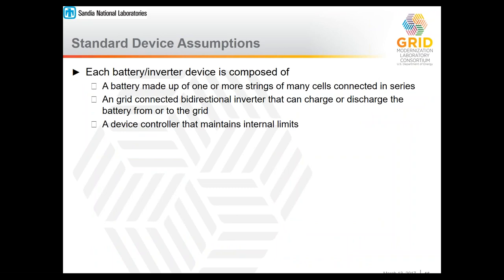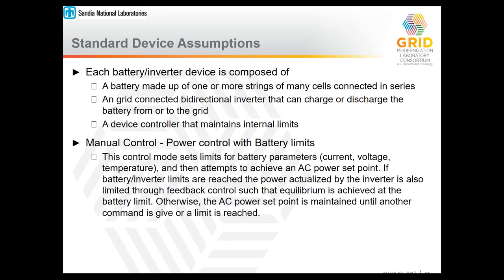So some standard device assumptions here. Just to further clarify what we're referring to, each battery and inverter device is composed of the battery itself, a bidirectional inverter that can both charge and discharge from the grid, and a device controller that maintains internal limits. How you control that device? There are many different ways to control that device, including automated and manual control options. But the one I'm going to refer to specifically to emphasize the behavior of how it actually works is this manual control, power control with battery limits.